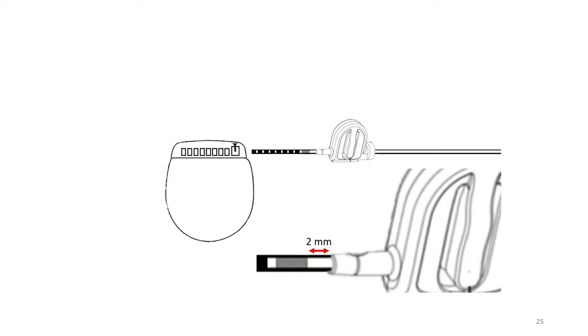If it is difficult to introduce the cable despite using this technique, and even though you have opened the locking screw enough, then you might try the insertion tool provided by Abbott. I myself have never needed this, but I have tested it and it can be helpful. Place the cable in the groove in the tool and close it. The tip of the tool should be about 2 mm from the closest contact.